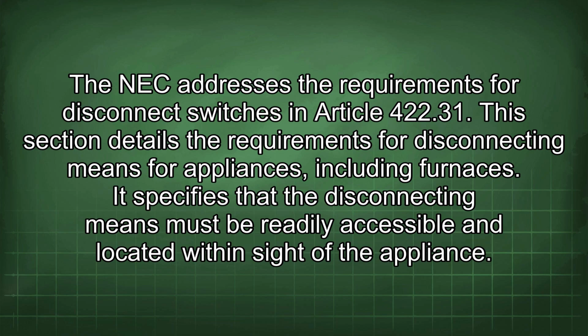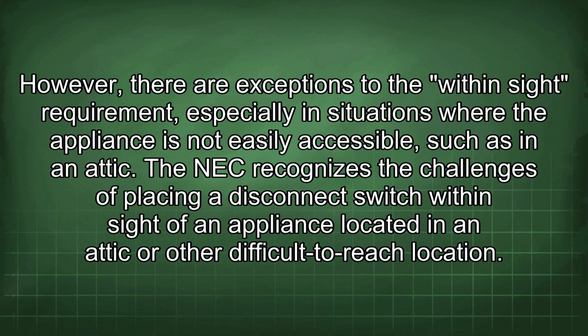The NEC addresses the requirements for disconnect switches in Article 422.31. This section details the requirements for disconnecting means for appliances, including furnaces. It specifies that the disconnecting means must be readily accessible and located within sight of the appliance. However, there are exceptions to the within sight requirement, especially in situations where the appliance is not easily accessible, such as in an attic. The NEC recognizes the challenges of placing a disconnect switch within sight of an appliance located in an attic or other difficult-to-reach location.